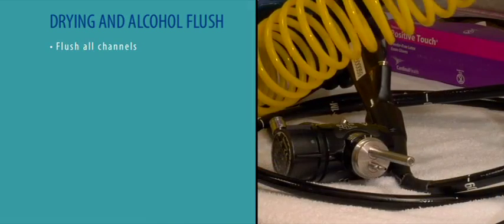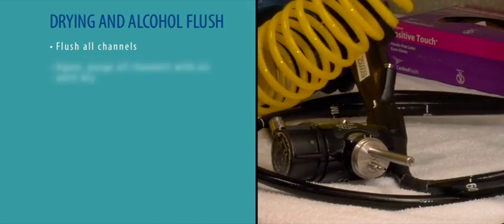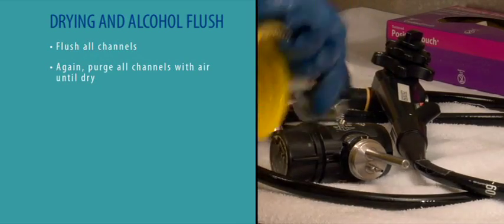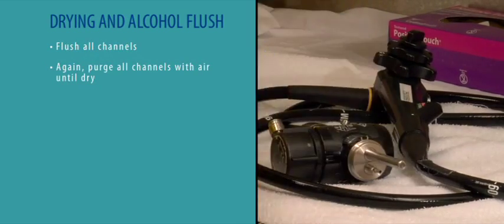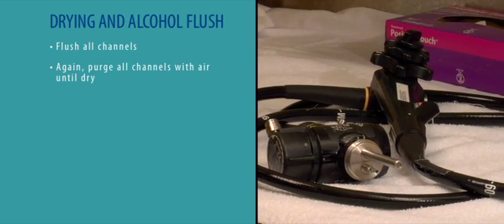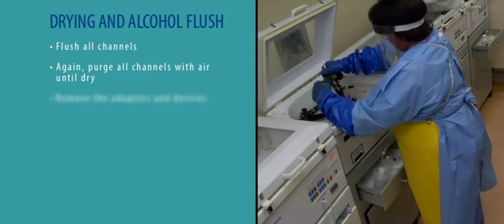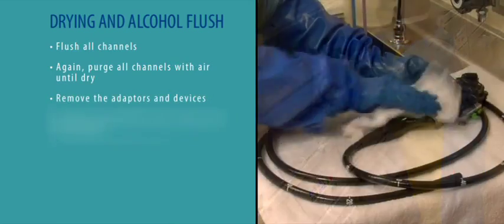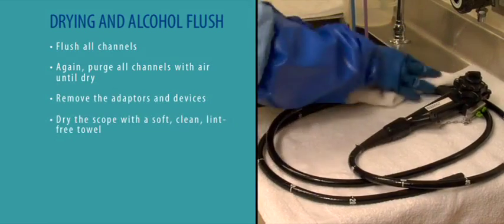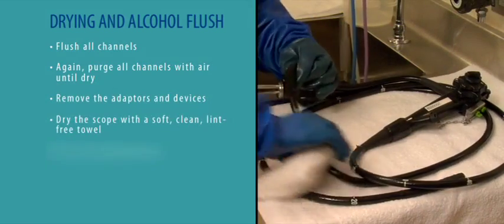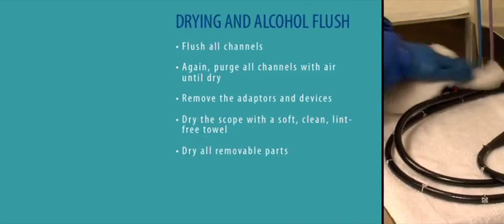After the alcohol rinse, again purge all channels with air until dry. Air may be provided by a central air source, a pump or compressor, or canned air. Avoid excessively high pressure. Remove the cleaning adapters and devices. Dry the exterior of the scope with a soft, clean, lint-free towel. Dry all removable parts.